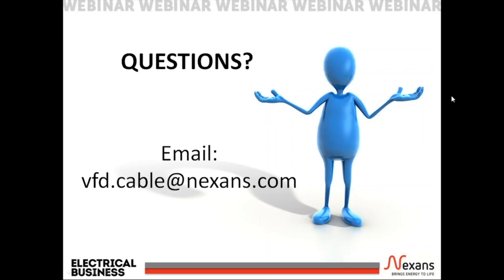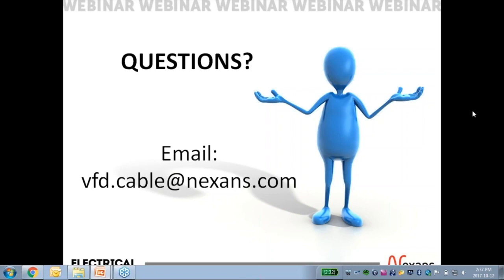Now, of course, Isaac, I was expecting this question to come up at some point. Could you discuss some of the price differences, a comparison of tech versus VFD cables? Whether that's expressed as a percentage or a dollar value, I leave up to you. One of the good things about being involved at Nexans and the technical group is I'm somewhat disconnected from the commercial side. So commenting on price, I don't know that I can off the top of my head say what percentage one's worth more than the other and so on. There may be a slight adder, let me put it that way, for the VFD cables versus a Tech 90 cable or cable and conduit. Ultimately, there's really no choice. A VFD cable has to be used.